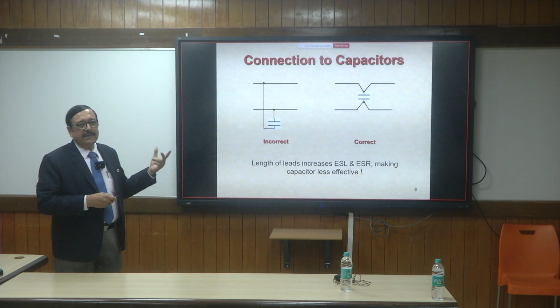We often have to put capacitors in parallel because it's not possible to operate without them - you may need a large microfarad value that isn't available, or even if available, the size may be too big to fit in the box, so you use a lower height and put multiple capacitors instead.